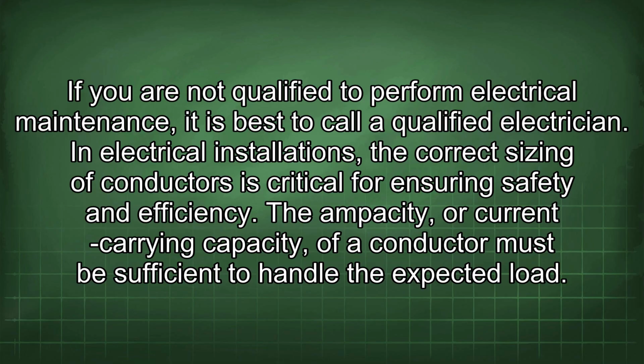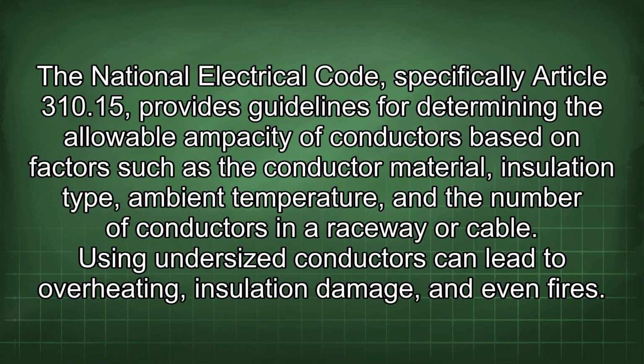In electrical installations, the correct sizing of conductors is critical for ensuring safety and efficiency. The ampacity, or current carrying capacity, of a conductor must be sufficient to handle the expected load. The National Electrical Code, specifically Article 310.15, provides guidelines for determining the allowable ampacity of conductors based on factors such as the conductor material, insulation type, ambient temperature, and the number of conductors in a raceway or cable.